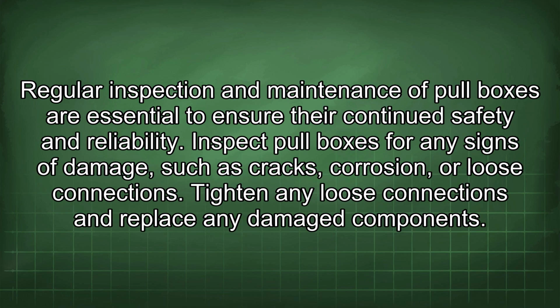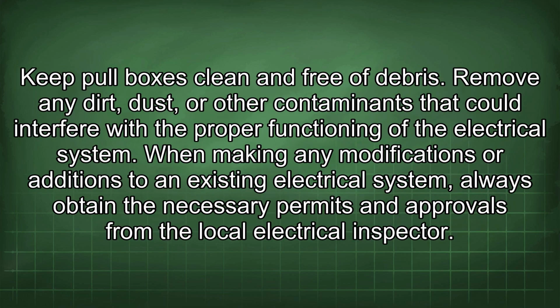Regular inspection and maintenance of pull boxes are essential to ensure their continued safety and reliability. Inspect pull boxes for any signs of damage, such as cracks, corrosion, or loose connections. Tighten any loose connections and replace any damaged components. Keep pull boxes clean and free of debris. Remove any dirt, dust, or other contaminants that could interfere with the proper functioning of the electrical system.